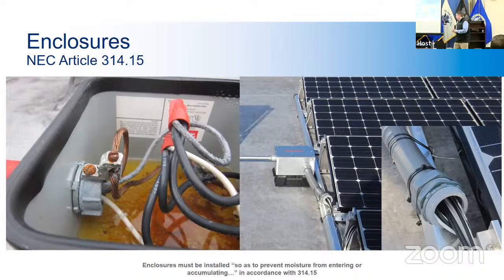And then over on the right, you have these two pictured, the same thing. This is a close up. This is a flat roof with solar panels on it. And someone put a conduit coming out of this enclosure that is pointed up to get over the racking. What happens when you do this is when it rains, the water will just go right in, and then it drains into the enclosure, causing problems, obviously. So you want to keep your eye out for situations where rain can get in and, you know, pool in an enclosure, or get in any kind of contact with electrical wires.